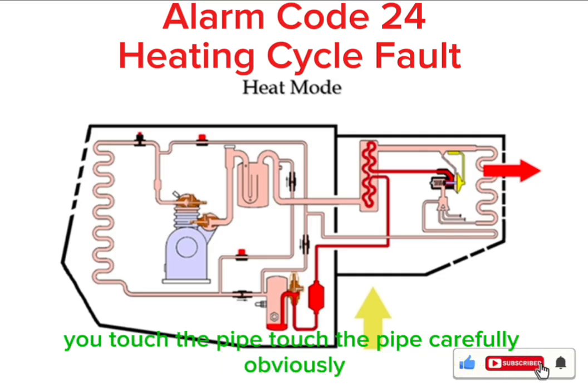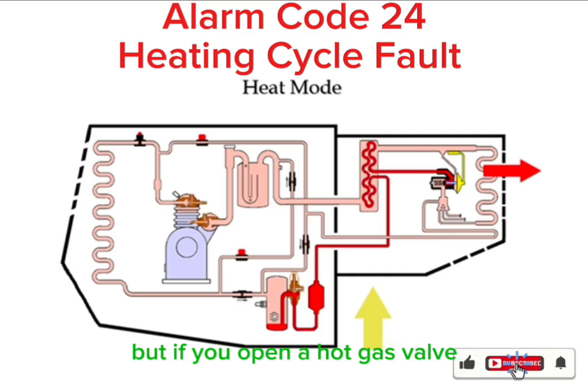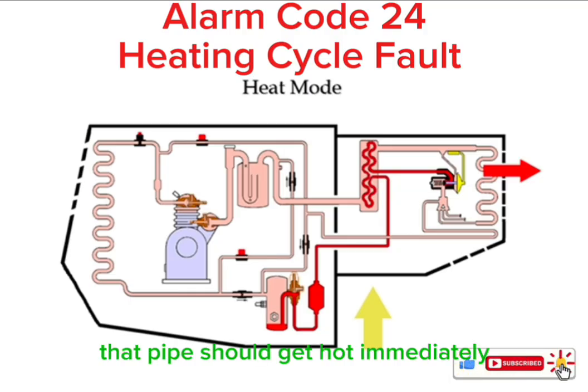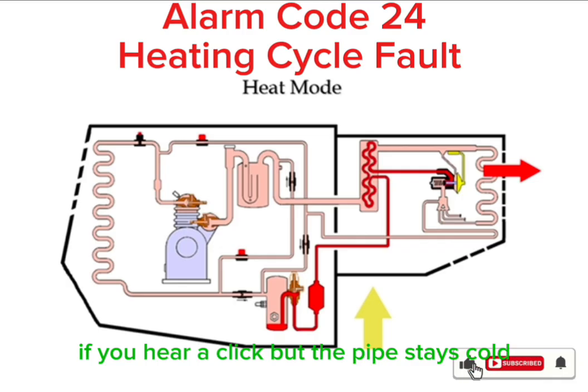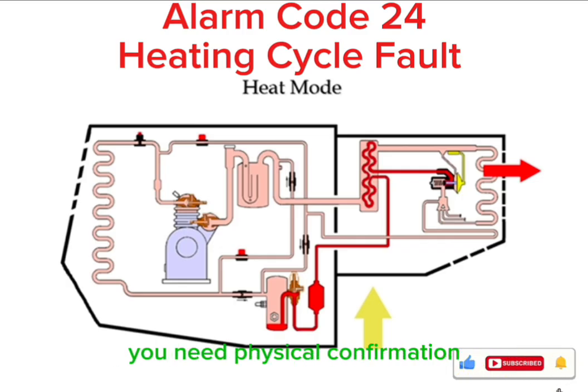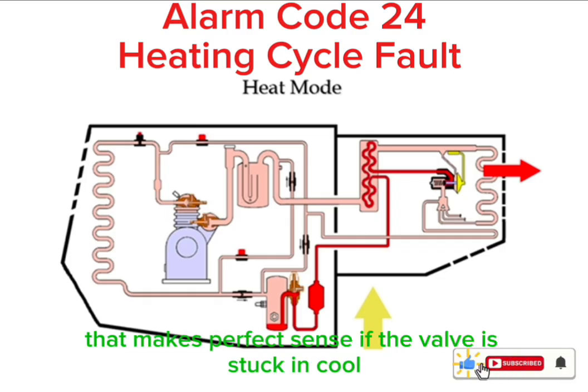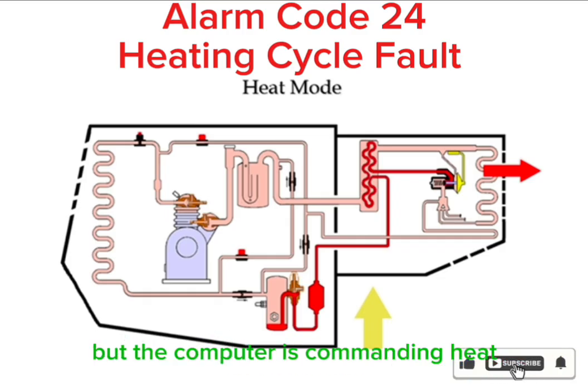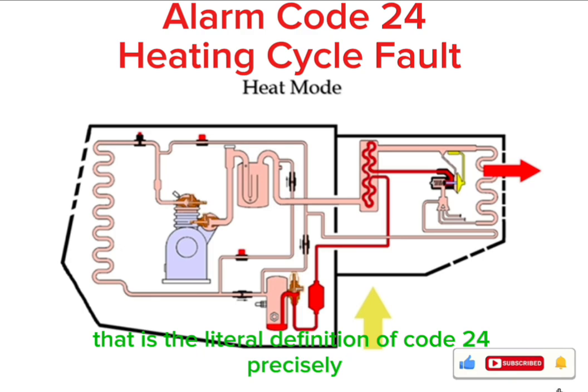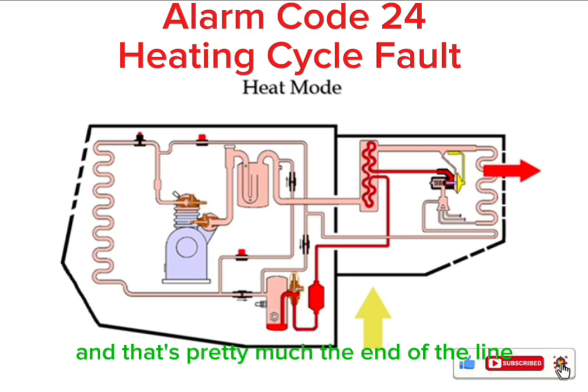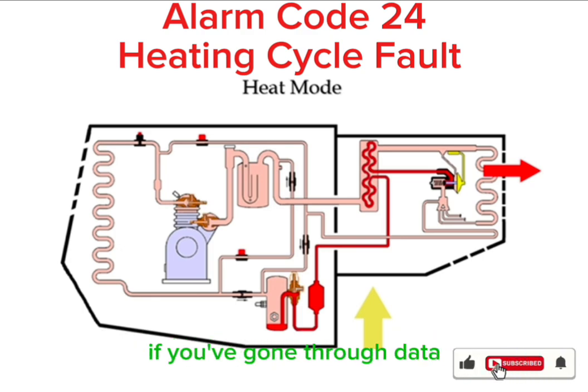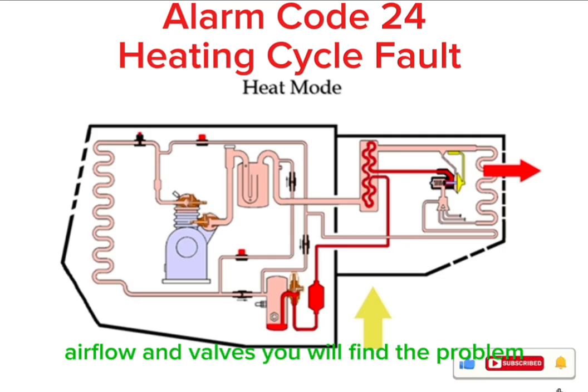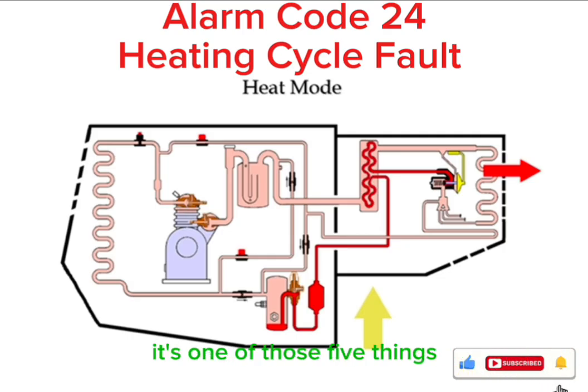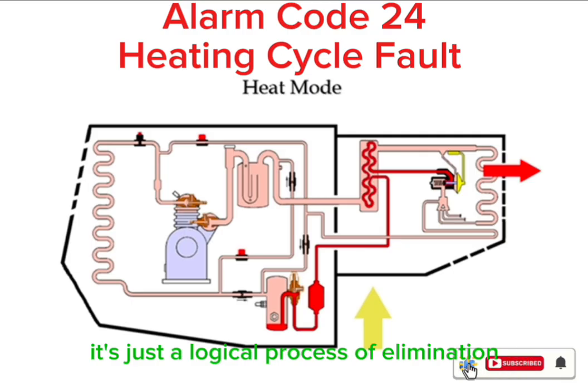You touch the pipe. Touch the pipe. Carefully, obviously. But if you open a hot gas valve, that pipe should get hot immediately. If you hear a click but the pipe stays cold, your valve is stuck. Or watch your gauges. You should see a pressure change. You need physical confirmation. That makes perfect sense. If the valve is stuck in cool but the computer is commanding heat, that is the literal definition of code 24. Precisely. And that's pretty much the end of the line. If you've gone through data, charge, sensors, airflow, and valves, you will find the problem. It's one of those 5 things. It's just a logical process of elimination.